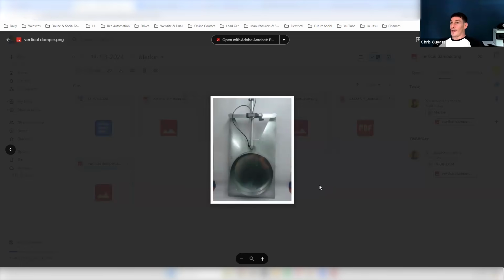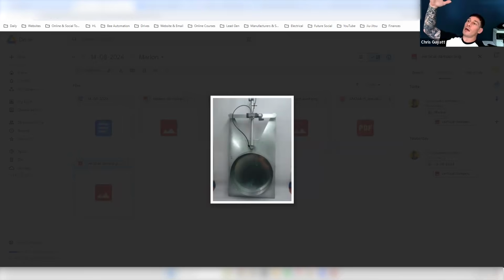We've got two of these, and literally we're just sending power until it goes all the way to the top. We're still applying power, we're not cutting power, but it just stops at the top or it stops at the bottom. So we've got no modulation, there's no real control, it's just opened or closed. It's almost like a digital signal, there's nothing in the middle. It's either fully open or fully closed.